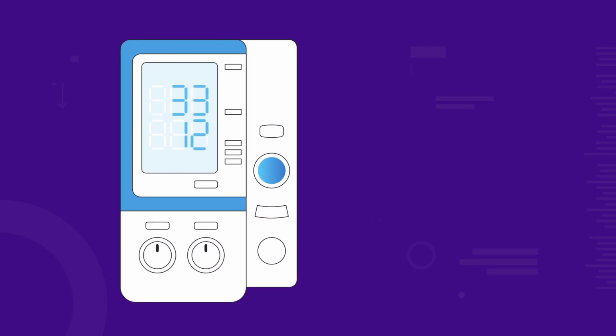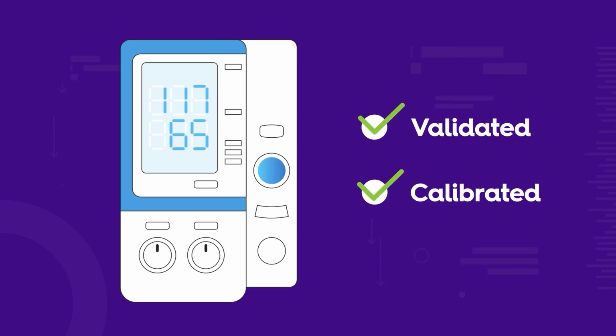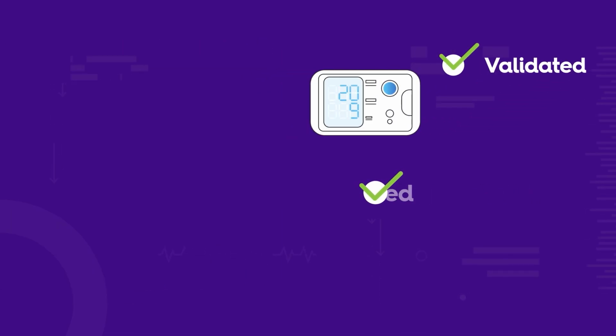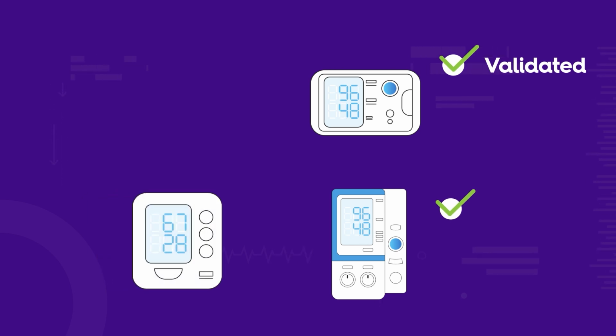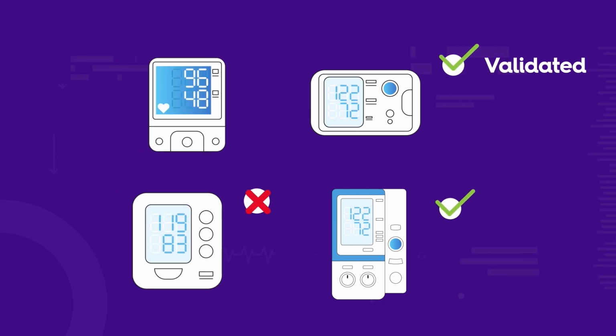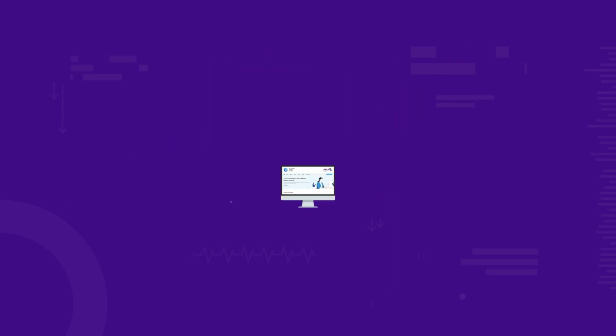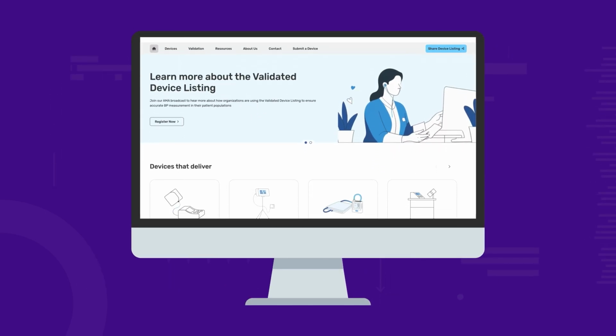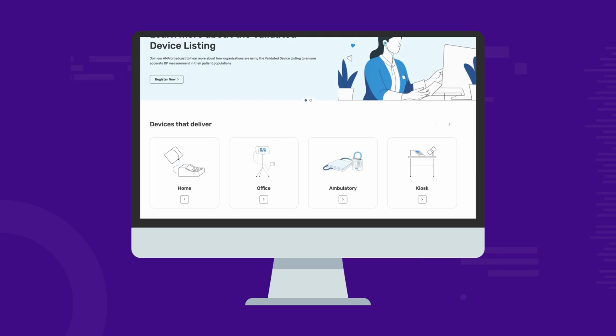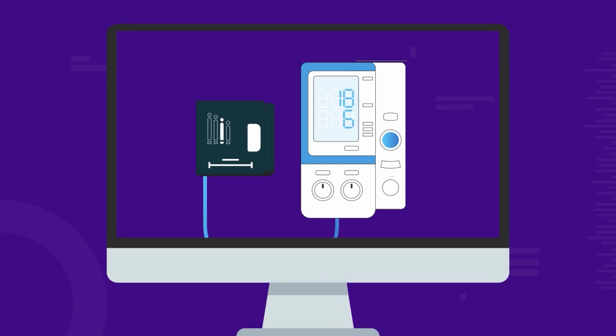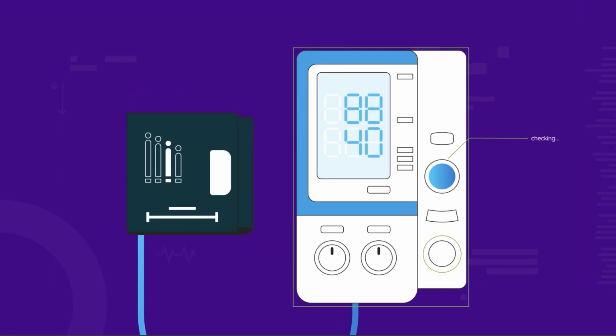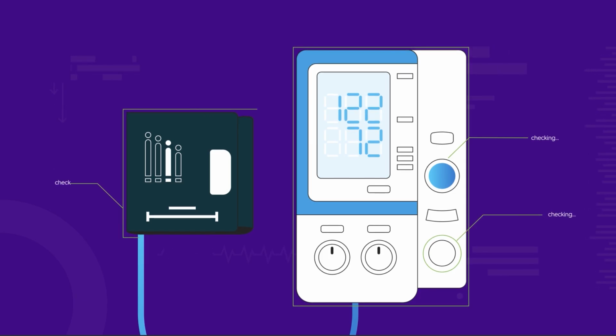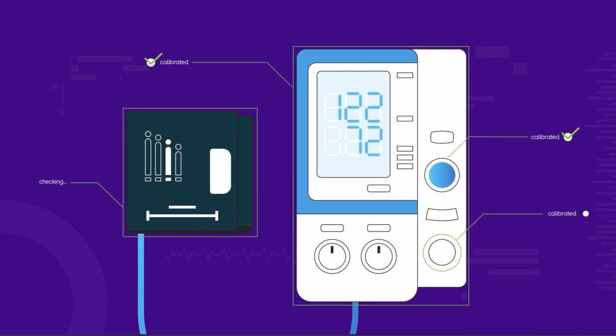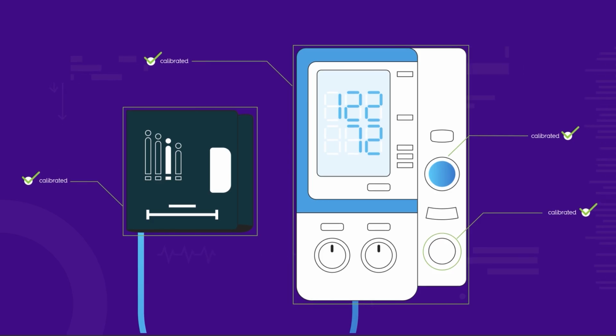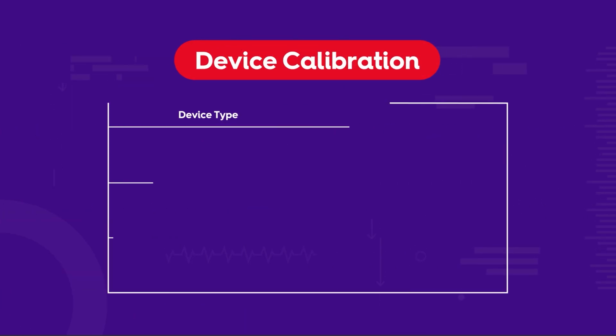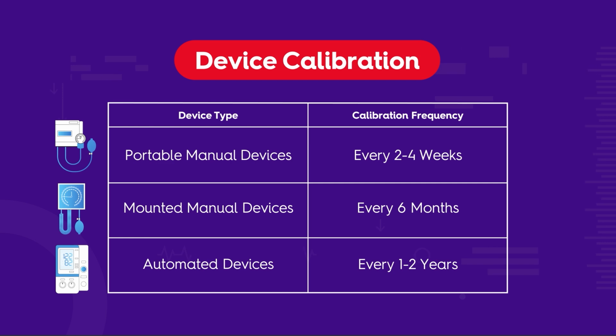Blood pressure measurement devices should be validated and calibrated. Validated devices have been tested for clinical accuracy using a specific protocol with the testing done by qualified independent measurement experts. There are lists that can be consulted to find available validated devices for purchase in the United States and internationally. Calibration involves assessing a device and its components to make sure everything is functioning properly. Calibration is often performed by a biomedical department or vendor. The frequency of calibration depends on the type of device.